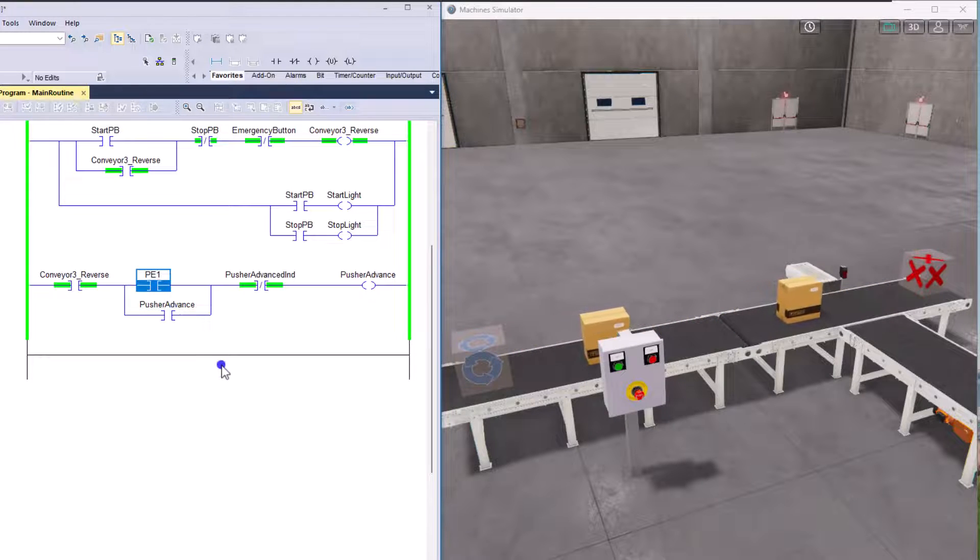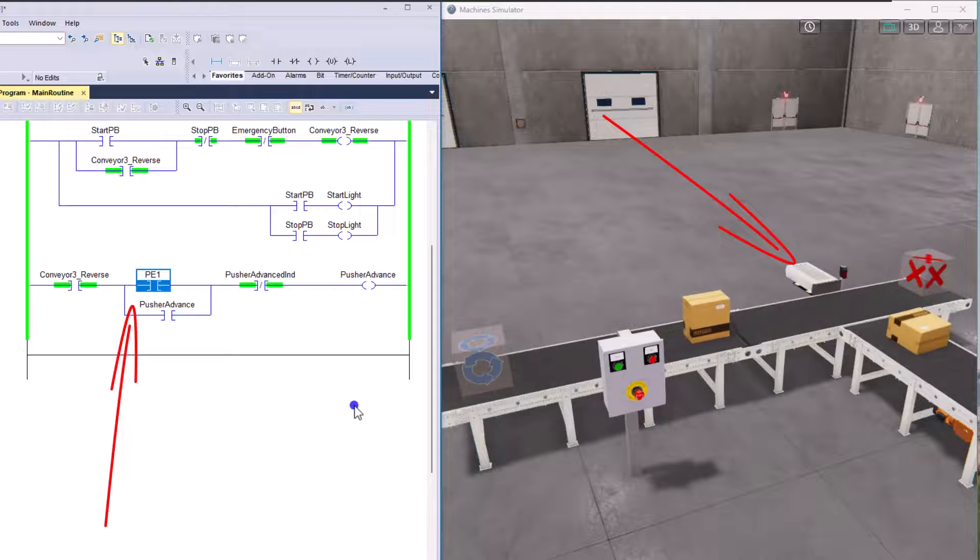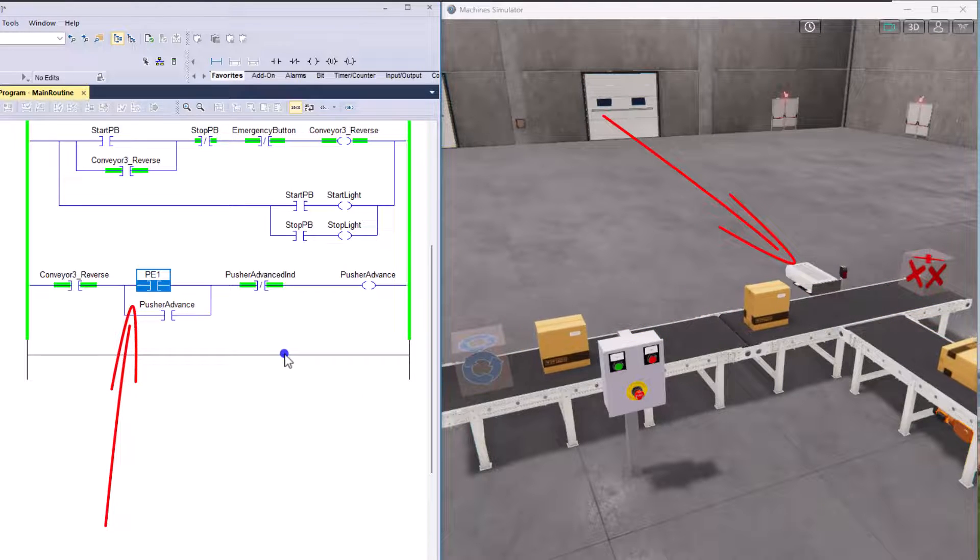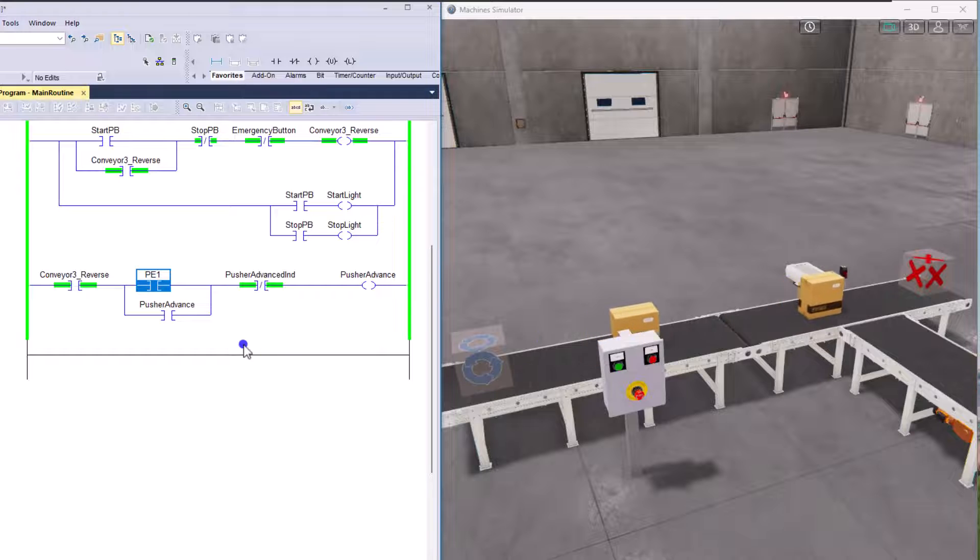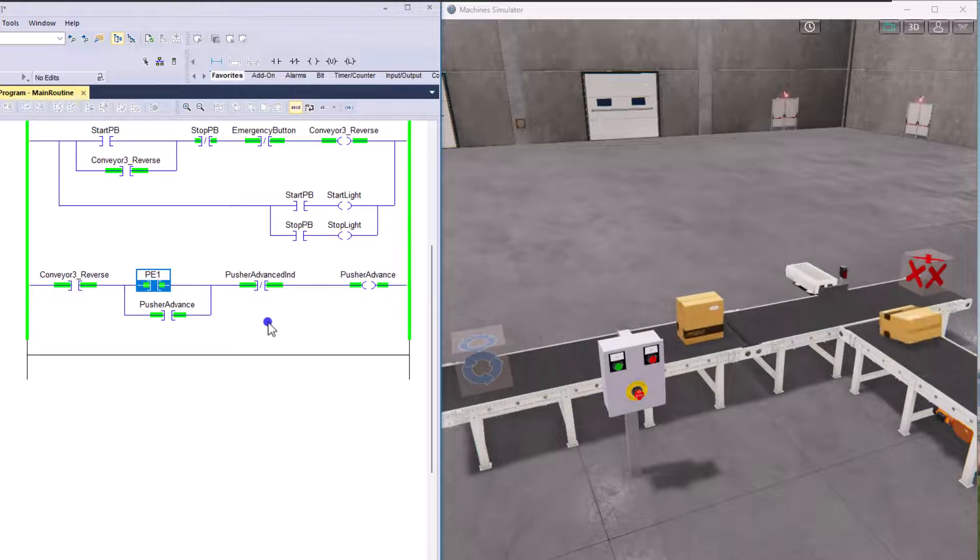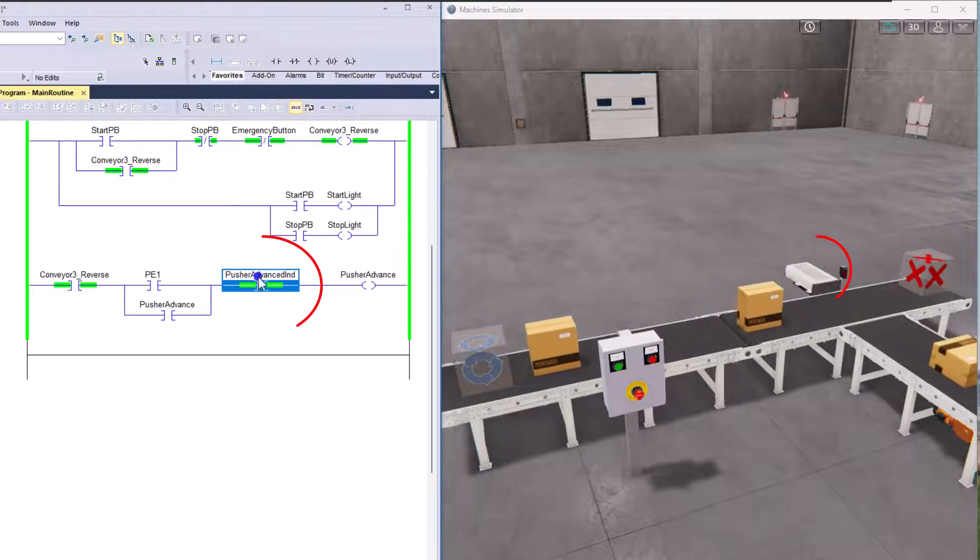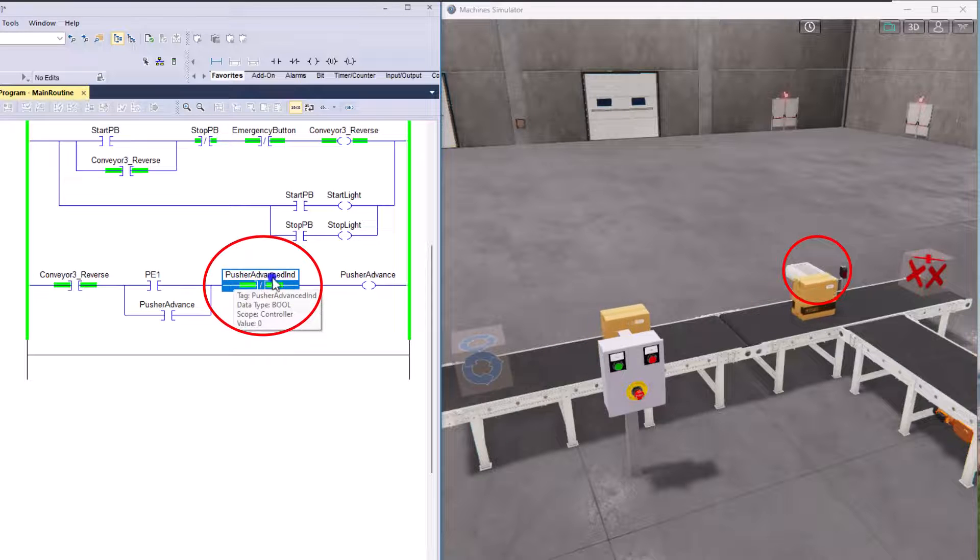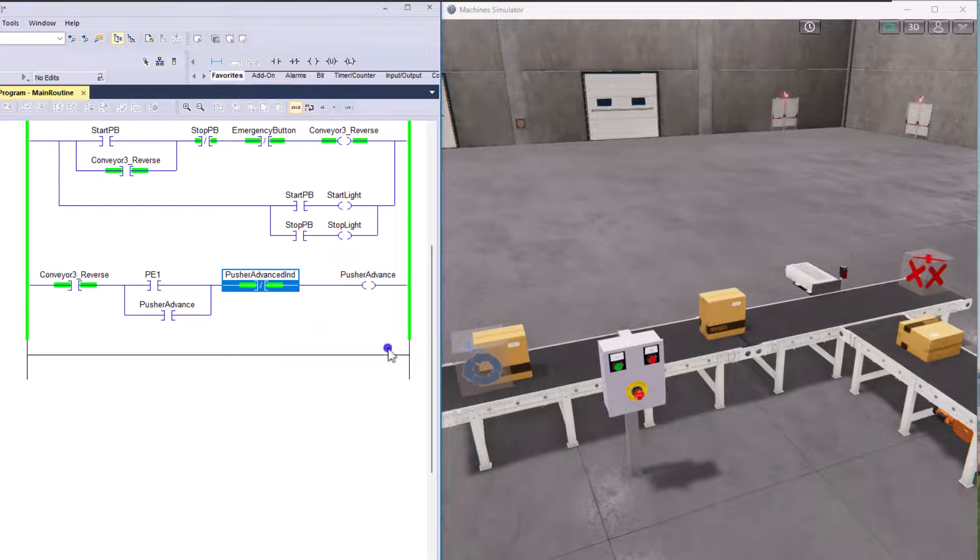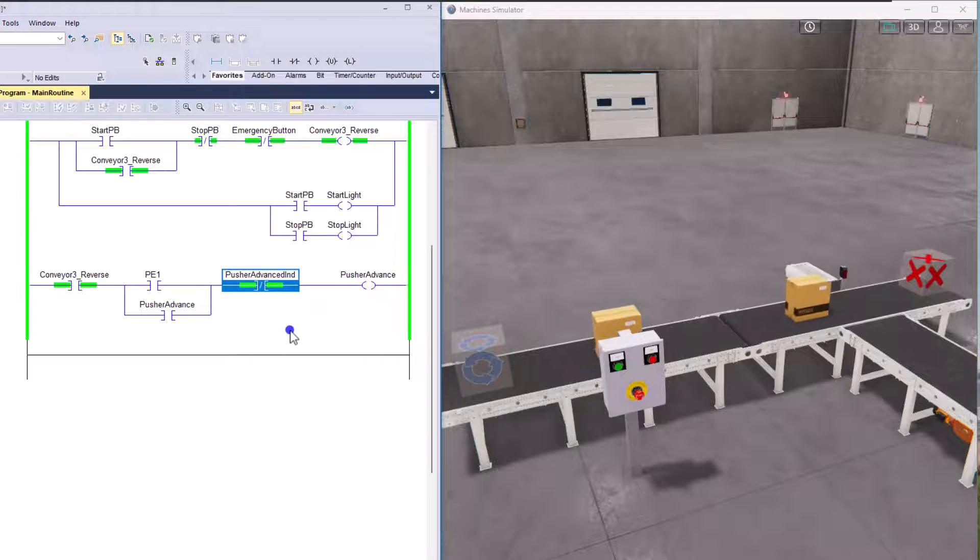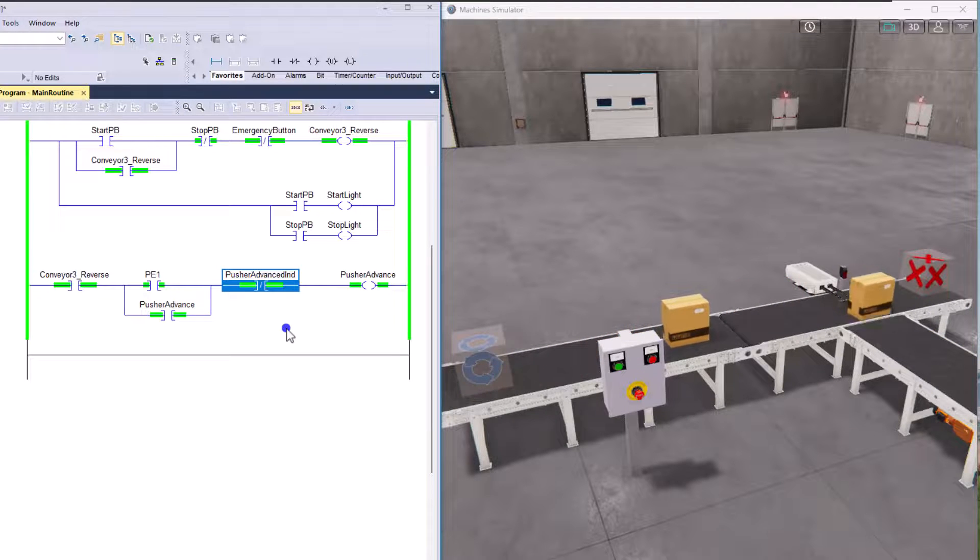Photo-eye one will come in and then the pusher will index out and then come back in, right? So as soon as it pushes out, it returns back in and how it returns back in is this pusher indicator. So there's a prox switch on the end of this pusher that lets it know that it's actually actuated out or actuated in, right?